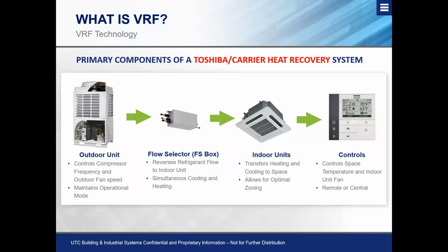Now, the other differences between the carrier and the Toshiba carrier, outside of where we separate that refrigerant into different states, is with these flow selector boxes in the Toshiba carrier system, we have two different selector types. As you can see here on this slide, we have a single port box and we have a multi-port box. So depending on the configuration of that system and how we want to lay it out, we have a little bit more flexibility on the selector box types.